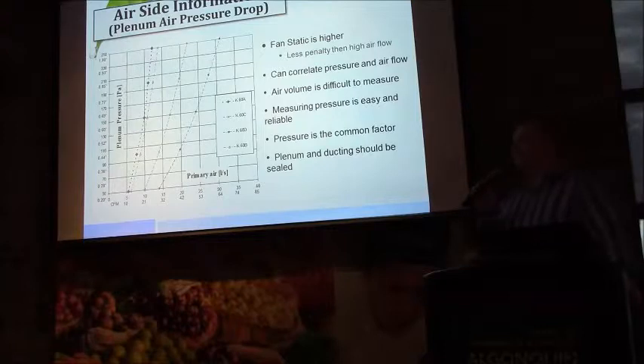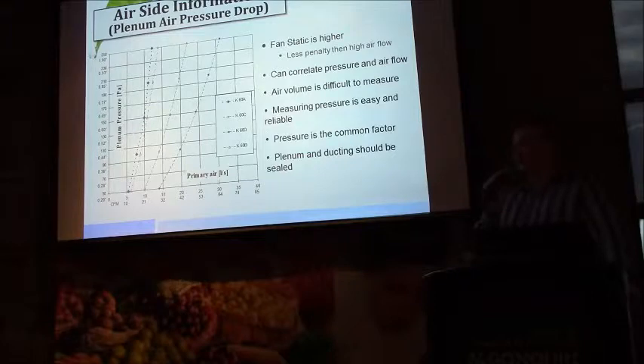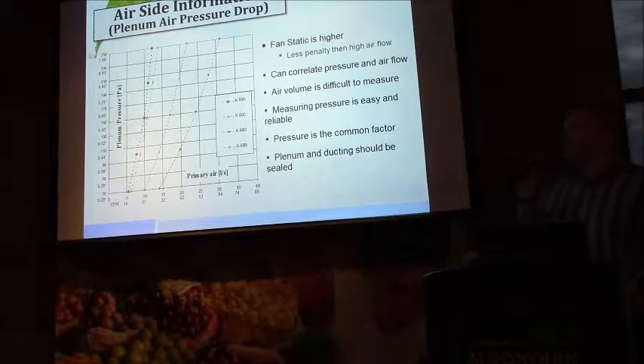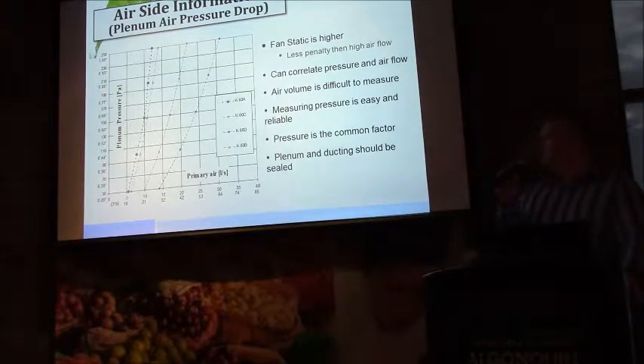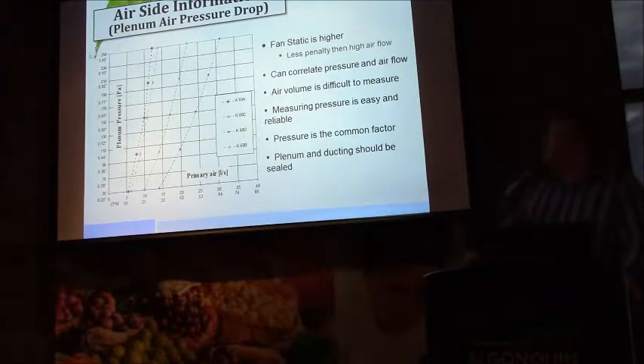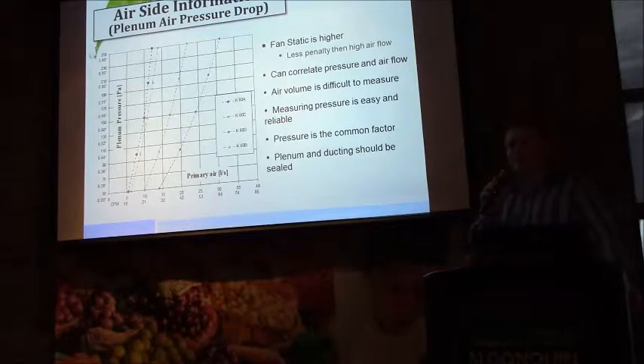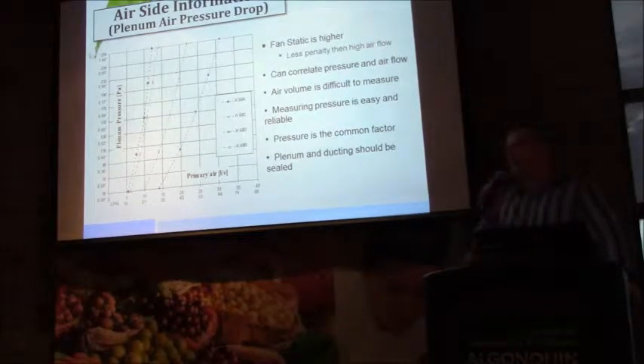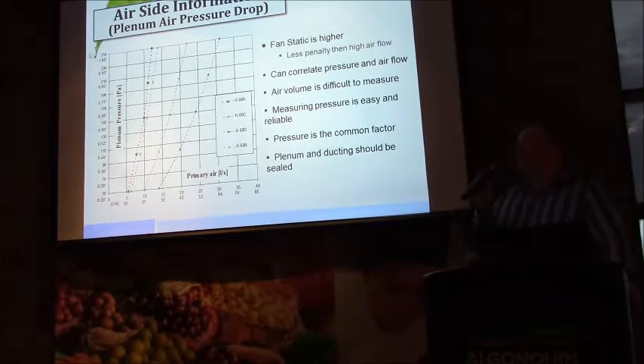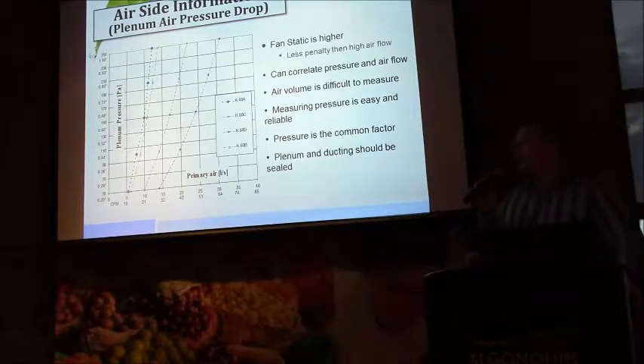Ultimately, the beams have come as an evolution to an existing design. An active beam is effectively an induction unit that's used a little differently from its inception as perimeter induction units. In any event, the higher the pressure that we have available to us at the beam, the greater the capacity, and generally doubling the plenum static pressure could conceivably yield as much as a 70% increase in capacity, which translates into obviously reduced capital expenditure because the beams can become smaller as a result.